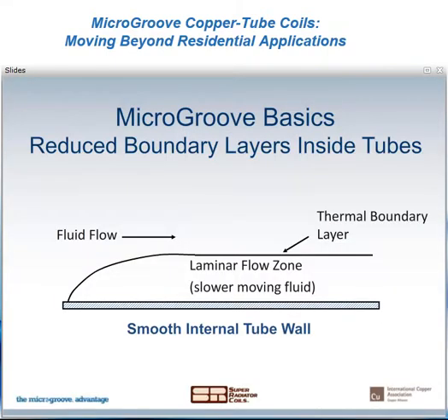Let's take a closer look at the reduction of boundary layers. And as I mentioned, boundary layers develop both inside and outside the tube. Here we're looking at the inside of the tube. Whenever fluid moves through a tube, the fluid that's closest to the tube wall behaves differently than the fluid in the center of the tube. And that fluid next to the tube wall moves slower than the fluid at the center, and a boundary layer forms next to the tube wall where heat transfer becomes much more difficult. And even in turbulent flow, a laminar sublayer forms and heat moves slower through these boundary layers than it does in the faster moving fluid that's toward the center of the tube. We need to remember that boundary layers act as an insulator and they interfere with the heat transfer that we really want.